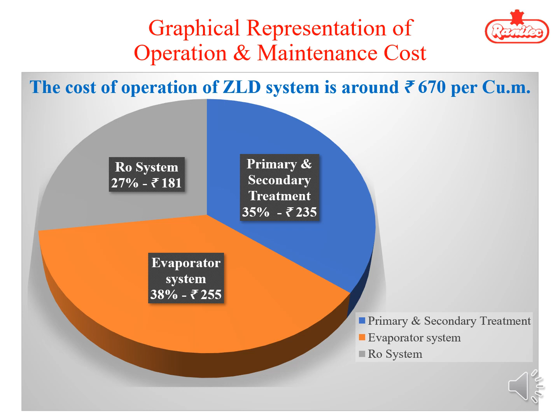This is the operation cost at the various stages. First, up to the primary and secondary stage, 35% of the cost is contributed, around 235 rupees per cubic meter of effluent. Second is the RO system, which contributes 27% of the cost, 181 rupees. And another one, the highest expense, goes to the evaporator: 38%, 255 rupees per cubic meter of treatment.